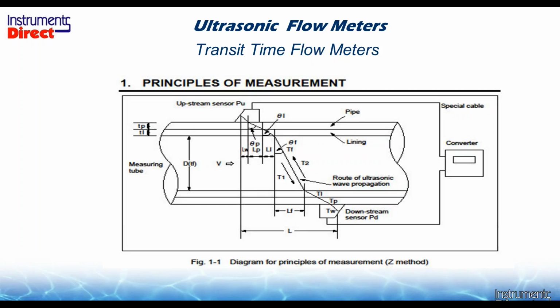Today's technology is doing more math, just like your iPhone's doing more computations for you, your portable ultrasonic flow meter is doing more computations for you. The way it works is we have a sensor here, and we have a sensor here, and we're going to put them on the outside of the pipe. The neat thing about an ultrasonic transit time meter is you know where the spacing is before you even put it on the pipe, because you program the meter, and the meter told you to put one sensor here and another sensor there. It can do that because each transducer has a crystal in it at a specific angle, and that angle is part of the math equation. Each transducer manufacturer has different angles, so you can't switch Siemens with a GE and a GE with a Dynasonics and so on. Everybody has a little bit different secret sauce in the angle of refraction that it comes into the pipe.